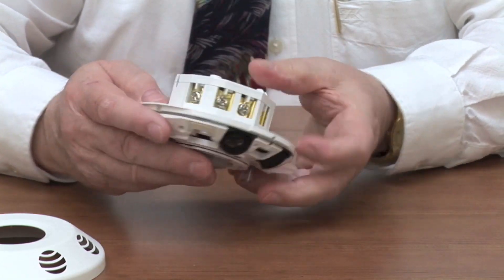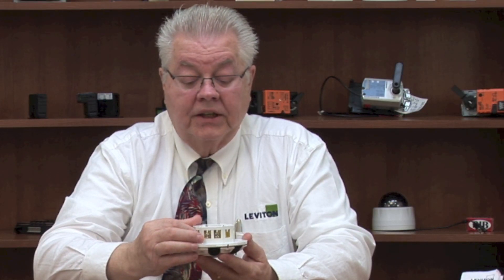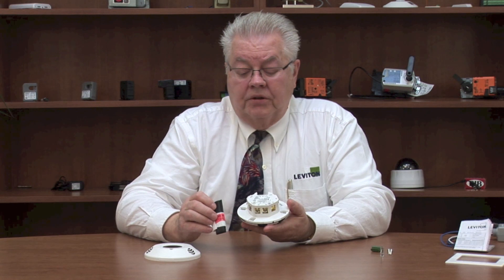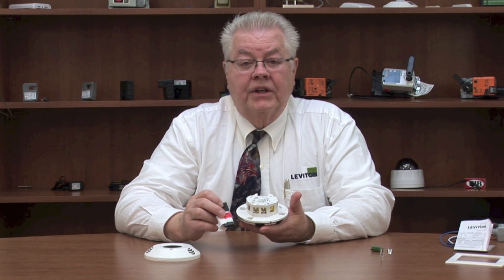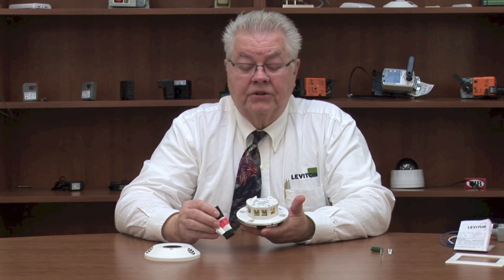It also has another feature — I'll show you the terminals on the side for the line voltage side. We also have low voltage normally open and normally closed type contacts. We have terminals for emergency circuits, which connect to your building management system. If you go into emergency mode, this will trigger the normally open contacts to normally closed, giving the lights power for egress in an emergency function.